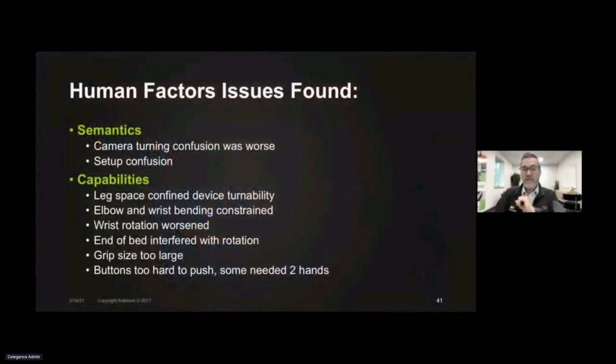Okay, so now in these formative studies, we're learning a lot of things, and this becomes more well documented. We have to test 6 to 8 users. We have to have a protocol that says what we're testing for, and then we have to see if what we're testing for was successfully completed in the test. Okay, but we discover more pain points, and that's what a formative study is for.